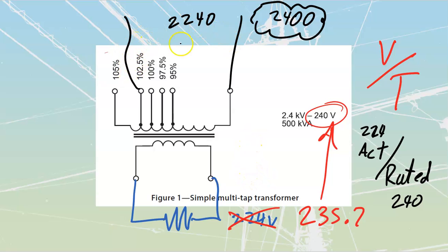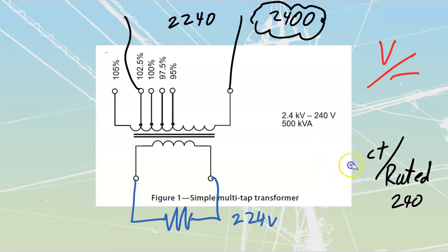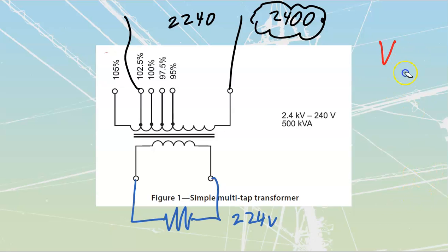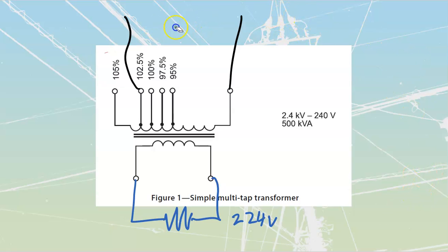If we come in on a higher tap, we would need to recalculate what we would have for all of our values coming into this one. Let's take a look. We're going to work with a new value of voltage just so we don't mix anything up. It's going to be close to my other one. And we will see what we get over onto the other side. Let's say that at this point, we're working with a value of 224 volts that I have across my load. Now, my load should have a value of 240 volts. We know that because that is the rating of our system.